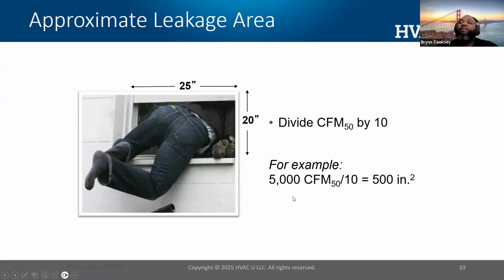So I go to a house and I want to evaluate a heat pump. I put the blower door in and I get this number. If I divide it by 10, this is approximately all the leaks inside the building shell together are going to represent a hole from inside to outside that large. Okay. If I put a heat pump in and I don't evaluate that shell leakage, I could be setting my customer up for some bad outcomes. Maybe I need to weatherize my building shell by air sealing, making this hole smaller and adding insulation in the walls and attic.